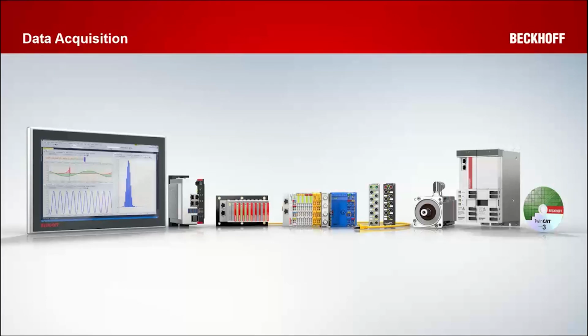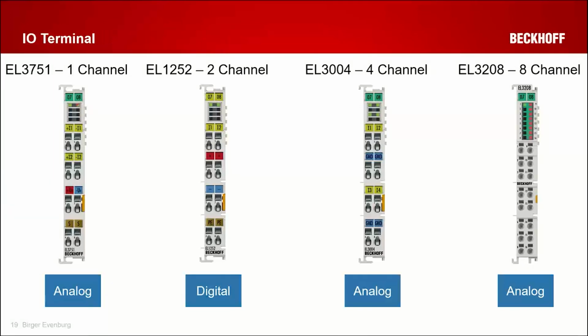But how does the data acquisition in the Beckhoff world work? Beckhoff EtherCAT terminals can have one input up to 8 or more inputs. An example here, we have one channel input, which can create one data point in the FlexMeter world. Or we have here a second terminal, which has 2 different digital inputs. Then we have a 4-channel input device or an 8-channel input device, for example.